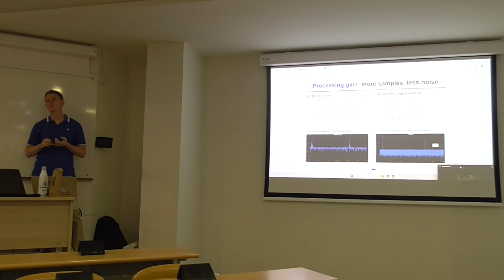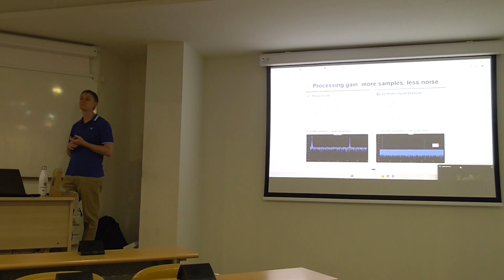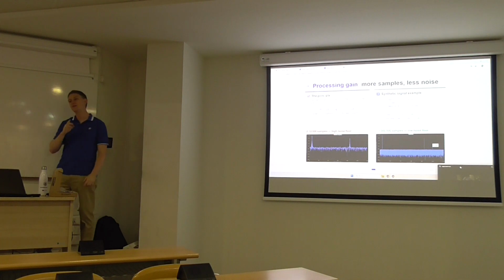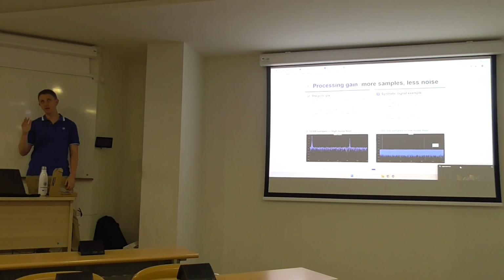Yeah. And I have seen motors of the same size, let's say 2-3 megawatt, and one motor has more than 100 slots, and the other has 80 or 70. So this is a very big difference, and through that you can make a serious error in the estimation of the speed. But in the methodology we developed, we are not using any kind of statistical information to ascertain the probable number of rotor bars. Statistical means that there are statistical outliers as well, and you can make a mistake. Yeah, but we are not using statistical information.